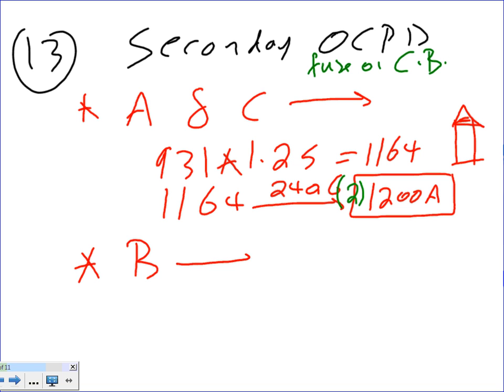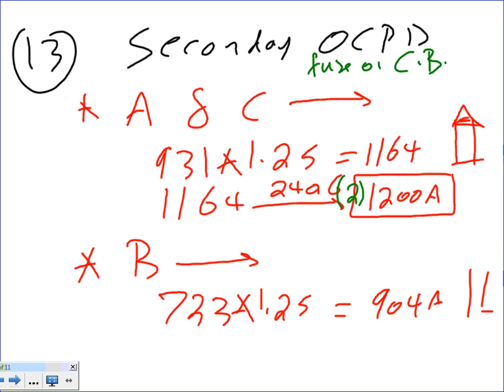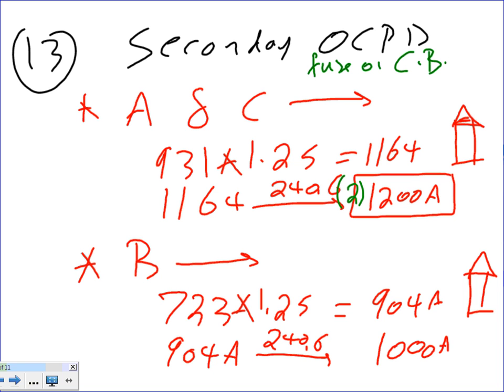Phase B, my friends, we had 723. Multiply this by 1.25. If you did your math, you're going to find it's 904 amps. Again, we're going to go up. 904 amp, take it to 240.6, and that will get you a 1000 amp. How many? One fuse. Why one fuse? Because one phase, or one wire.